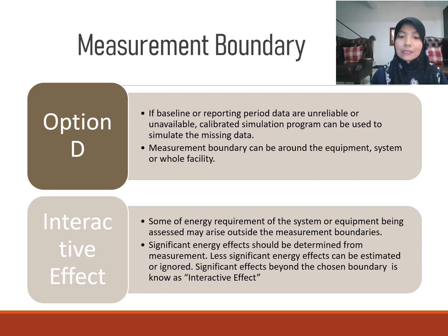A more detailed example of interactive effects. Consider a replacement of conventional, inefficient lighting with more efficient lighting with less power. The measurement boundary that you draw includes the power to the lights. Possible interactive effects that may arise from this ECM are lower mechanical cooling requirement, because less heat is dissipated from the lighting system, so less air conditioning is required. Raised heating requirement, in the case of a cold season country, where with less heat from lighting, more heating is required to heat the environment. Increased reheating of ventilation air, and increased plug load from new task lamps if you need more lighting.